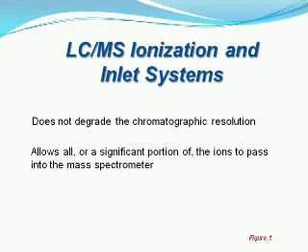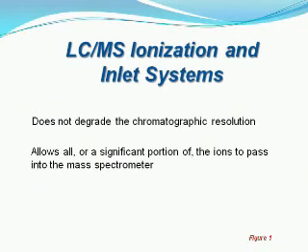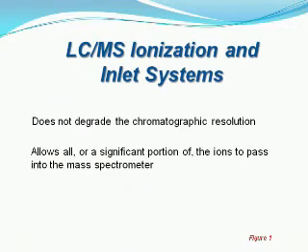The second requirement is that we want all, or at least a significant portion, of the ions that we form to pass into the mass spectrometer. LC-MS interfaces are not particularly good at this. The interface is quite good at producing ions of the analyte material — close to 100% of the analyte material is ionized — but only a very small percentage of that is actually sampled and taken into the mass spectrometer. Nevertheless, LC-MS interfaces have very high sensitivity and are capable of producing good limits of detection.